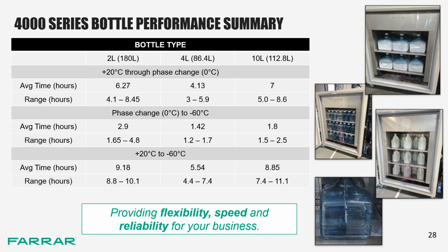So in this slide, we're looking at 3 sizes of bottles we looked at: 2 liters, 4 liters, and 10 liters. We added temp probes to each bottle in the center to determine the internal bottle temperature, so we can verify when it achieved the temperatures we've got here, in this case, minus 60 degrees C. And you can see this temperature probe design in that carboy picture at the very bottom.